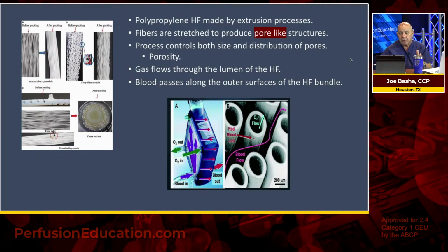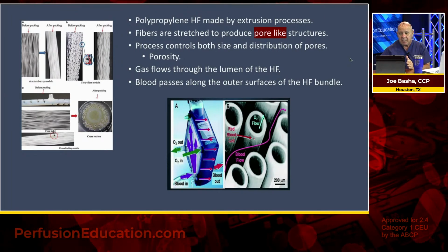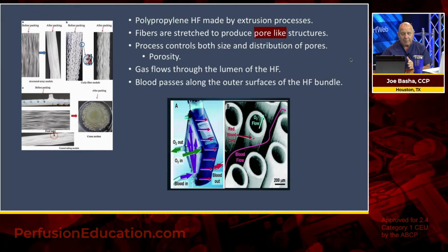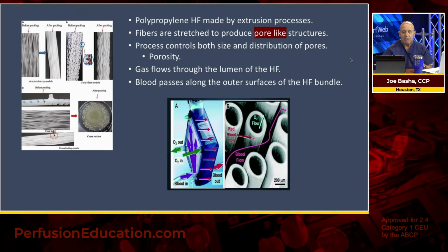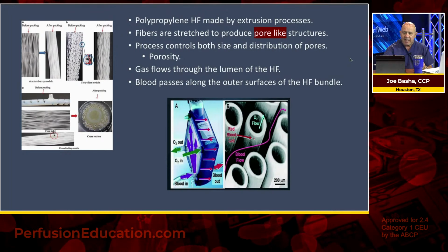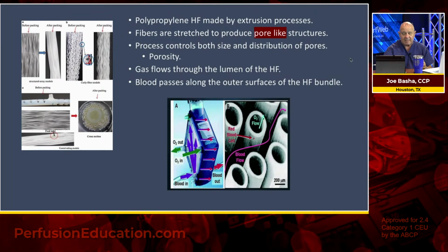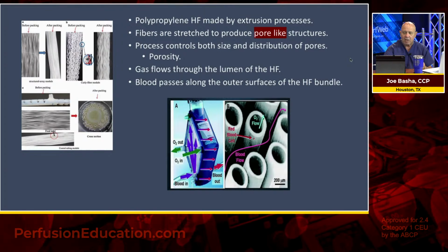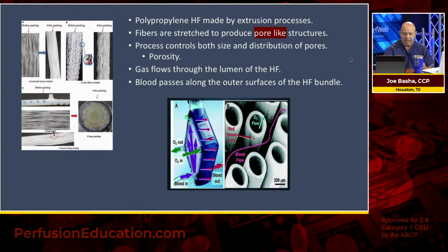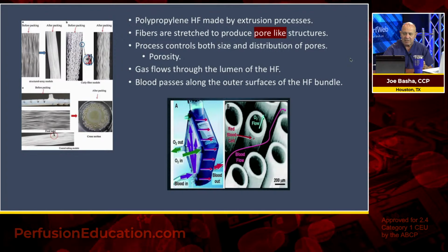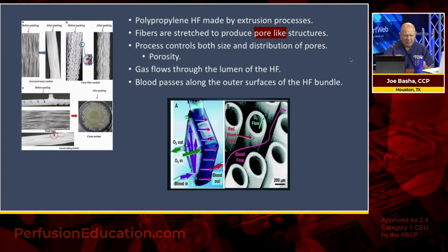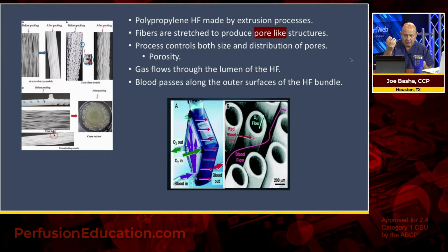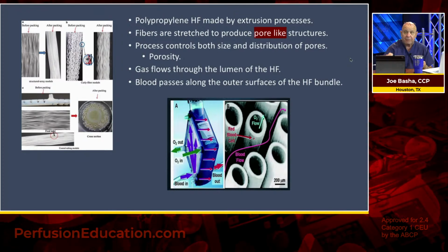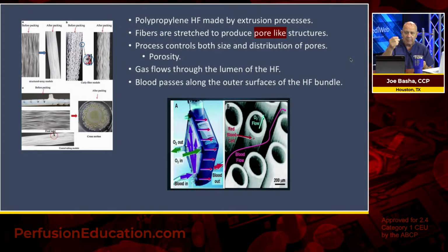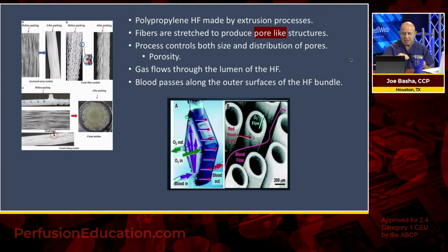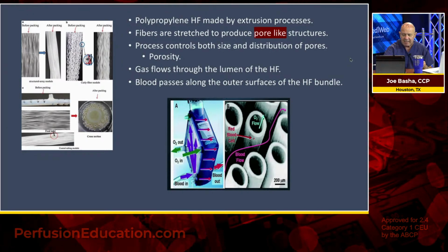Gas flows through the lumen of the hollow fiber. So again, it's central lumen. Blood passes along the outer surface of the bundle. So in an oxygenator, versus dialysis, which is central flow where the blood goes through the inside of the hollow fibers, in oxygenators it's on the outside, and it's represented down here.